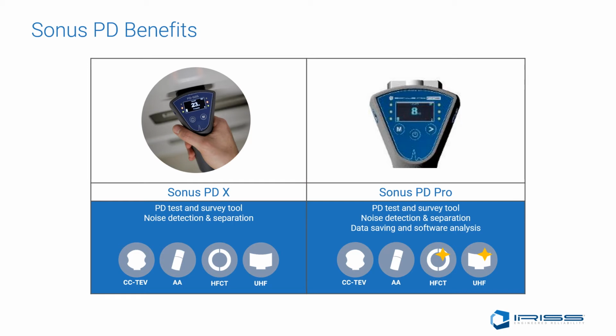With the addition of the HFCT clamp and the UHF transducer, inspectors can test other assets that were once untested when using ultrasound or TEV detection equipment for the location of partial discharge events.